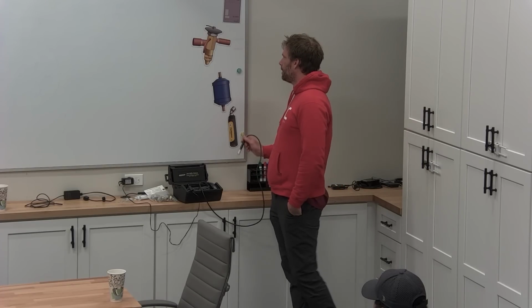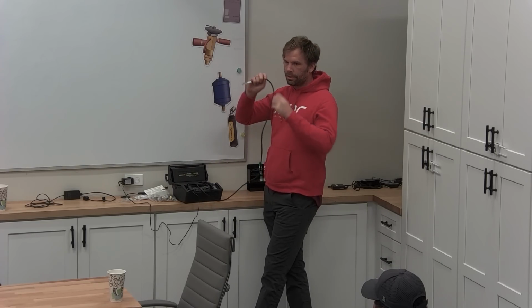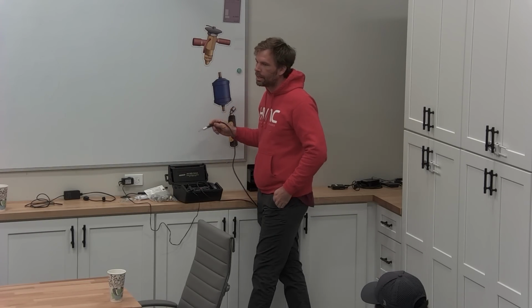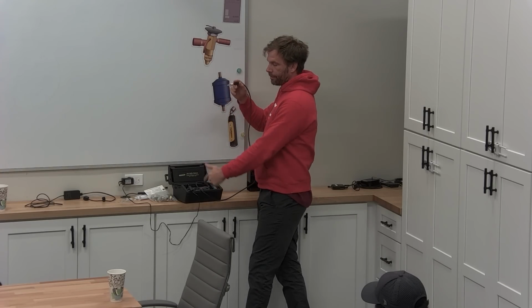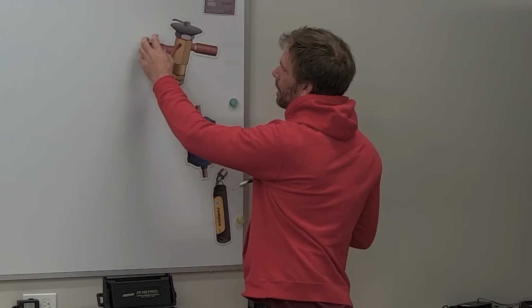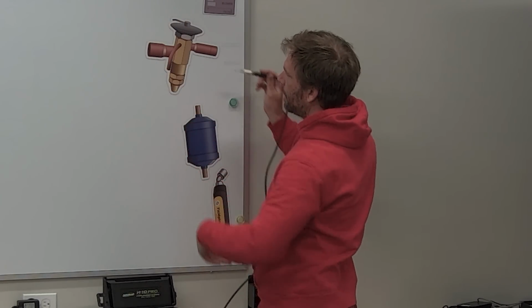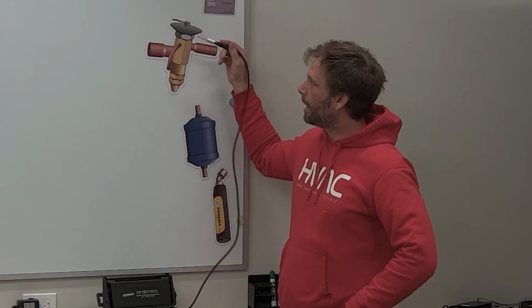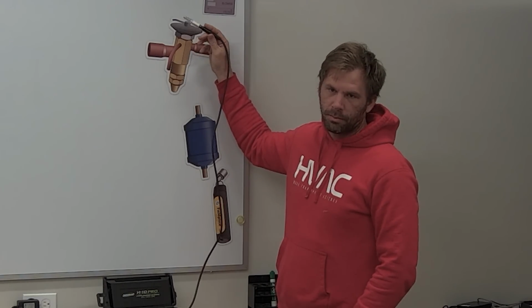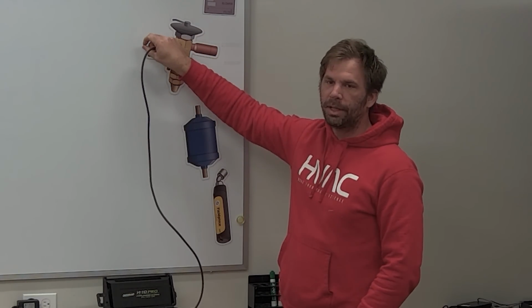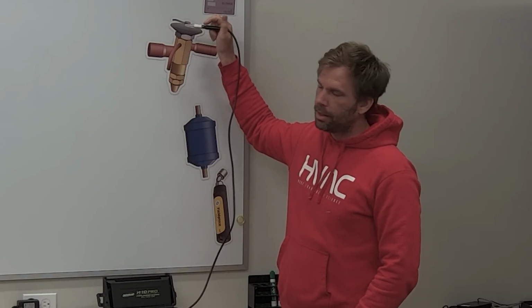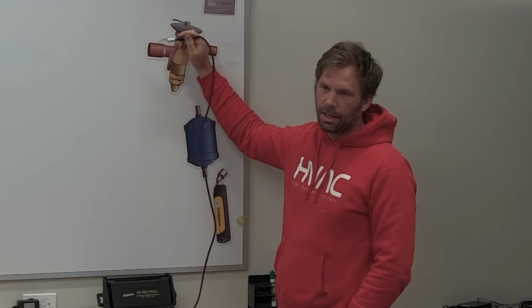Another common mishap on small leaks, and the reason we go and come back, is if you have a really tiny leak and it's just a little bit of refrigerant, and sometimes it's a little bubbly. If you put your bubbles on it, you see the bubbles kind of in spurts, not super consistent. This is sucking up air into the sensor, and sometimes you'll have that sitting there and this condensed air of refrigerant fills, and you come here a couple times with your leak detector and you actually suck that all in, and then you go back and you don't really get it exactly. Give it a few seconds for that refrigerant to show up in that really tiny leak, go right back to that pinpointed spot, and then you should get a hit.